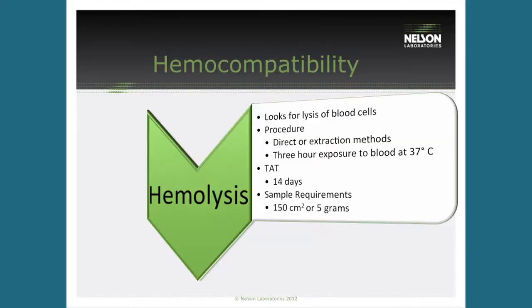This is Table 1 from ISO 10993-4 — it's supposed to help you evaluate what testing is necessary for your device. The concept is you go down the device examples, find the example that correlates best with your device, and it tells you what testing you have to run. Unfortunately, the FDA does not recognize ISO 10993-4, and the reason they don't recognize dash-4 is precisely this table — it doesn't really help as far as what the FDA recommends.